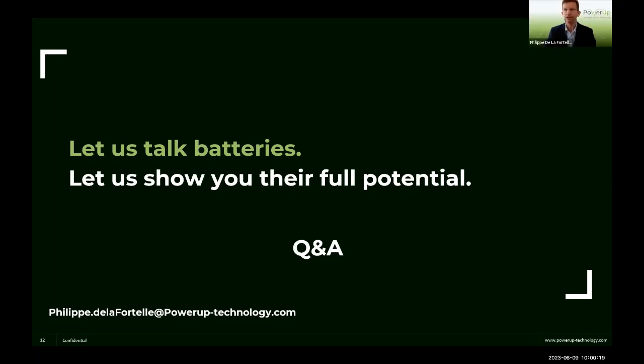Great questions. Thanks, Iman. So we are constantly helping our customers assess the safety level of their assets, right? And not only on continuous measurement, but also on, I would say, measurement of data after an event has happened to prove to them that our systems could have detected the safety event if they had had our solution implemented. And so we were able, for instance, to prove points that on a real safety event, we were able to detect early signs of the issue up to 9 months before the issue really happened. So that's truly interesting, because 9 months gives you plenty of time to organize the maintenance, to organize the swap of modules, and make sure that your safety event is under control.